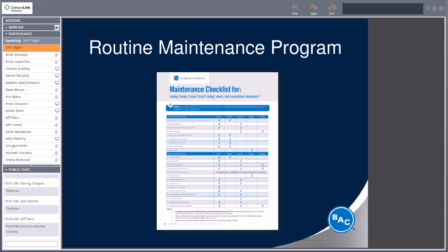Real quickly, it's got inspect the spray nozzles, drain the basin and piping. That is on startup. Check your water levels in both basins, whether it's a hot water basin or the cold water basin. Check and adjust the bleed rate. Generally, that's going to be done by your chemical treatment personnel. I don't have a lot of slides on chemical treatment, but at the end of the presentation, we'll spend some time talking. Chemical treatment and maintaining the materials and the metals in your tower may be as important as the preventative maintenance checklist that we're going to run through.